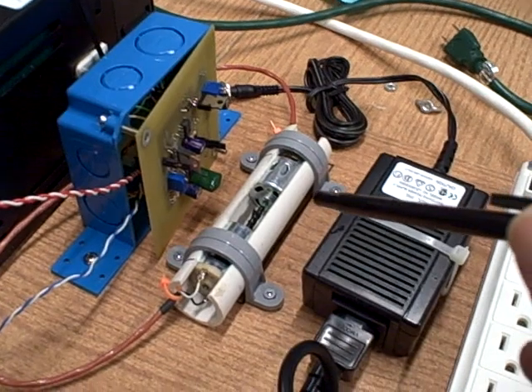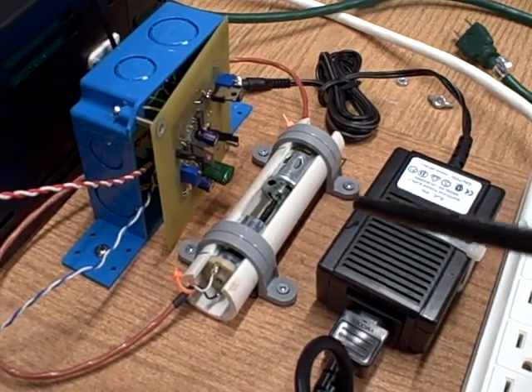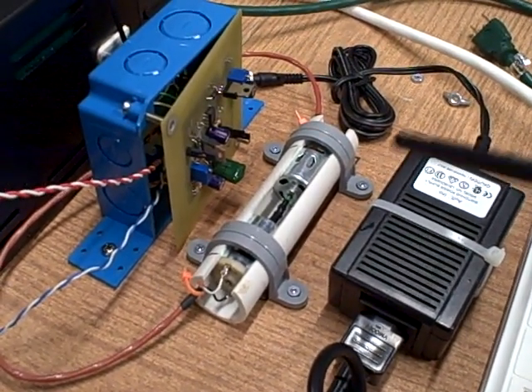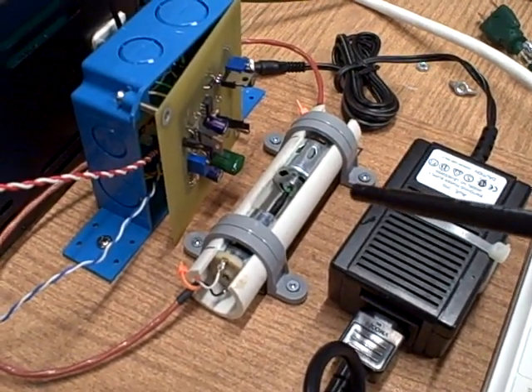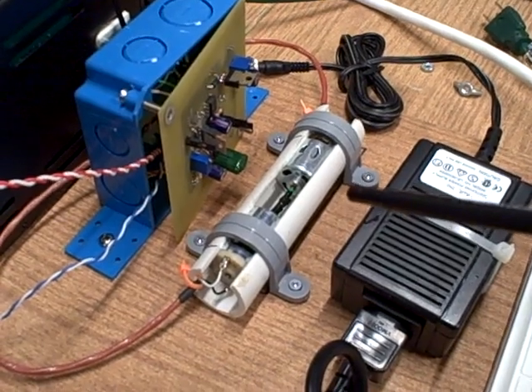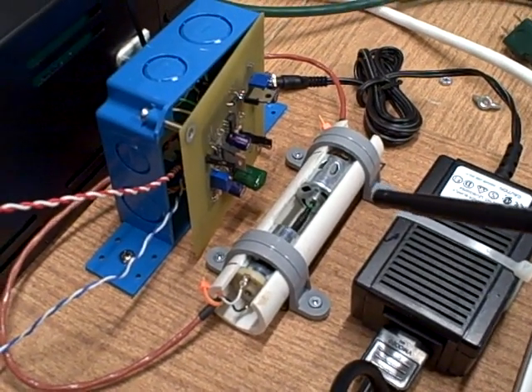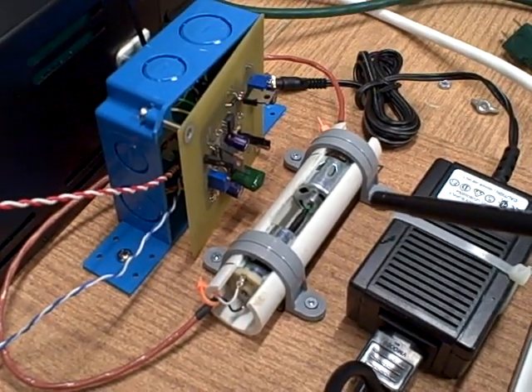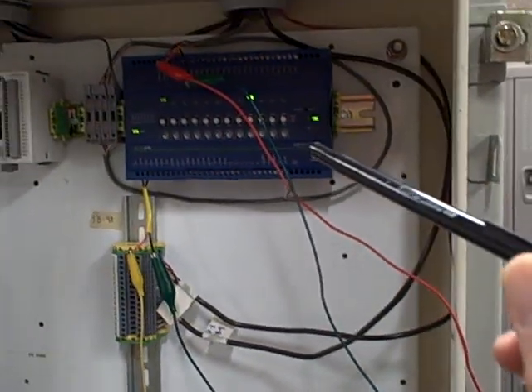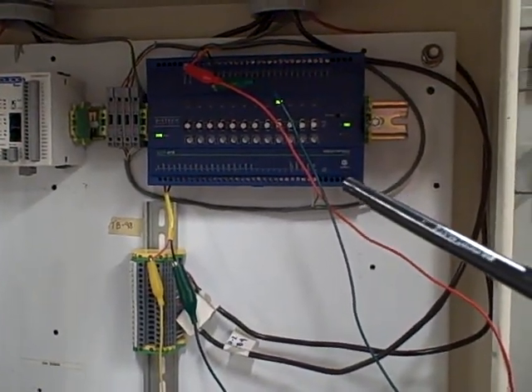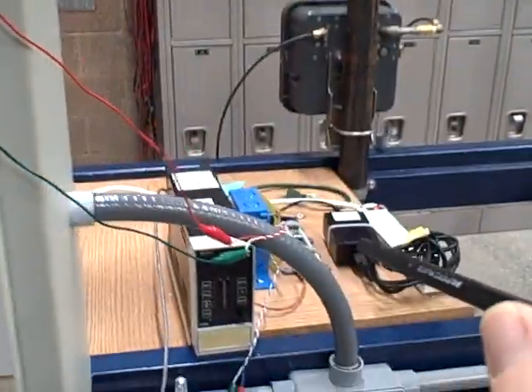Here with our process, motor speed control, the time constants are very, very short. This motor speeds up and slows down extremely rapidly compared to, let's say, the time it takes for a room to heat up or cool down. Therefore, the slow scan time and processing time of this controller is wholly inadequate for the task we're giving it right here with motor speed control.